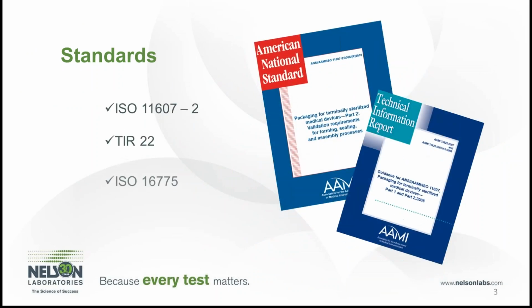To start off with standards, ISO 11607-2 is the main standard that we will be mostly talking about today. It is the standard that describes and goes over in detail what is part of a packaging validation plan. TIR 22 is a great resource to help clarify and add some detail to 11607-2.